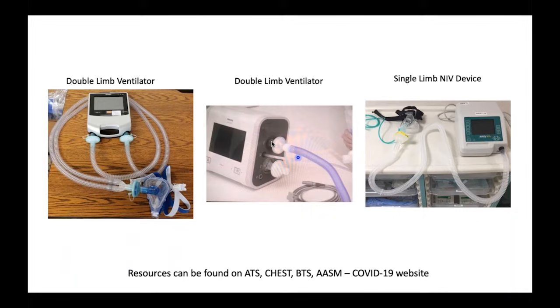This is another type here. This is the Evo from Philips. It's a double limb circuit. And this is the single limb. So if you have a BiPAP machine, you could do this, right? So you get one limb. This is that full face mask that's non-vented. And here's that little viral filter plus the CO2 exhalation port.